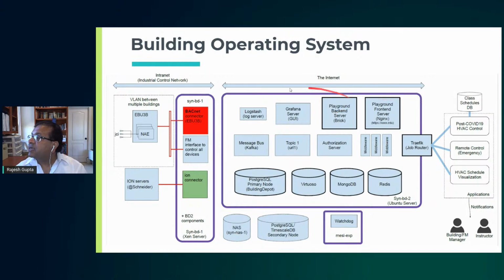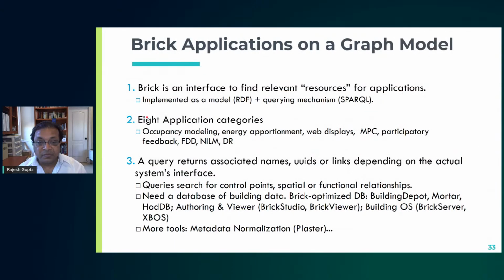So all your interactions are through the internet, but then of course you do have an industrial control network, which needs to be much more secure, and therefore for that particular LAN we usually use some kind of a BACnet connector to go from the internet to the industrial control network and back and forth, so that your application is run in the open network, and then the programs that are actually controlling building operating systems. It could be buildings, other cyber physical systems. It could be even more critical things, for example.